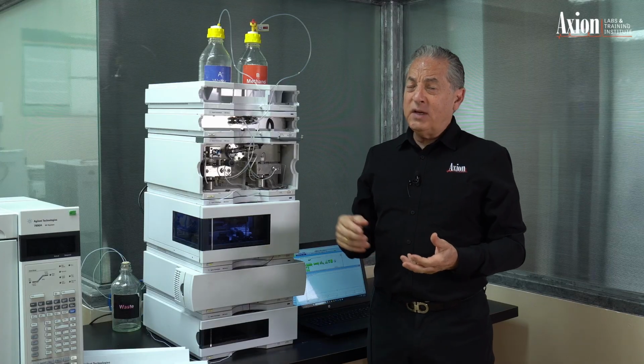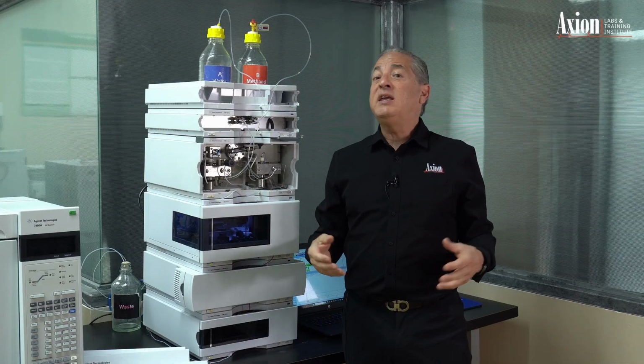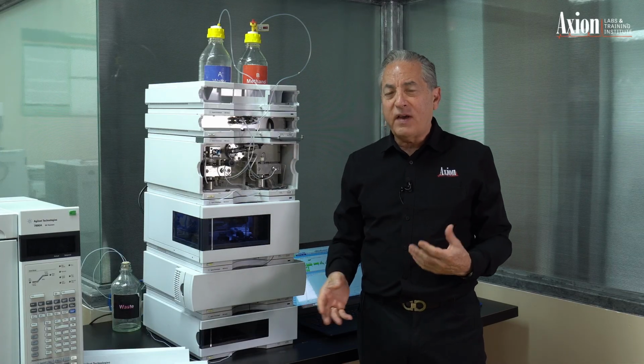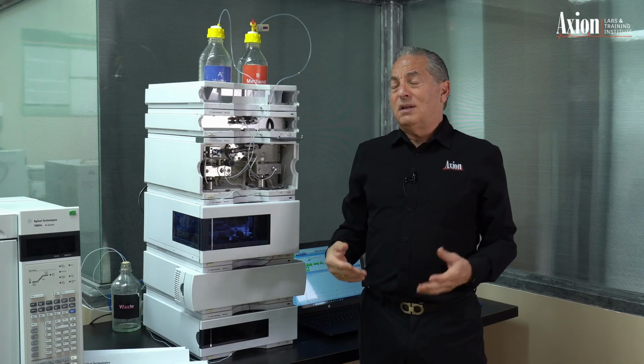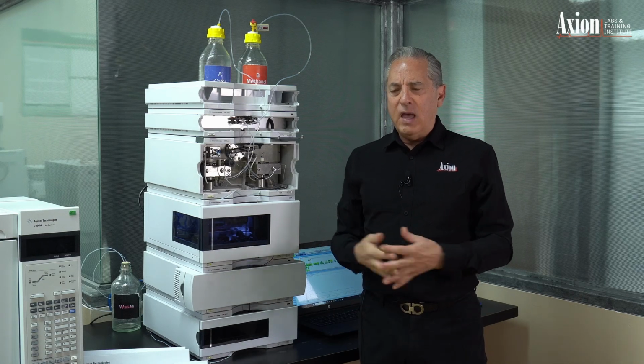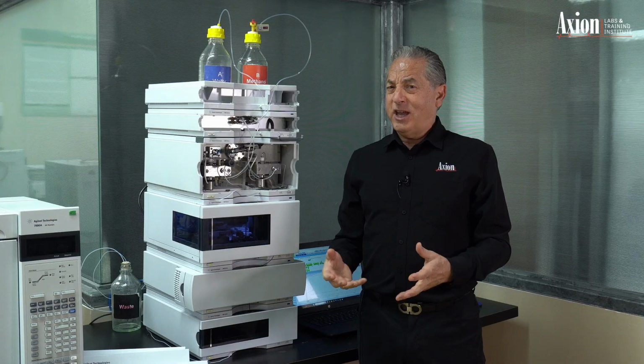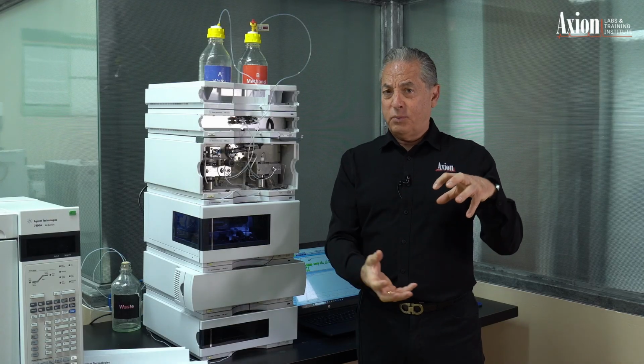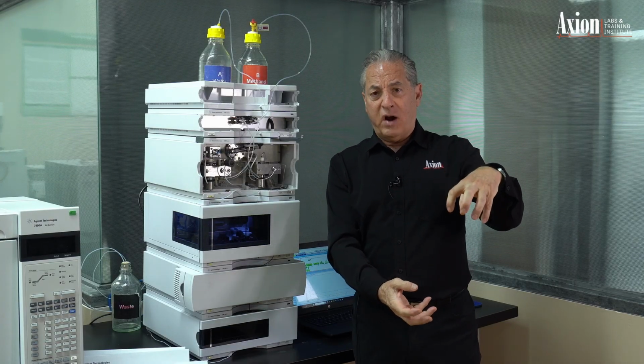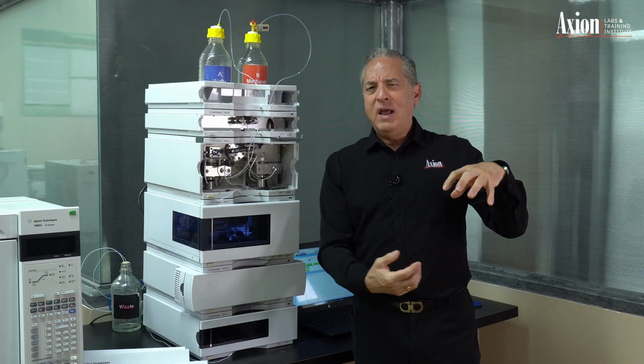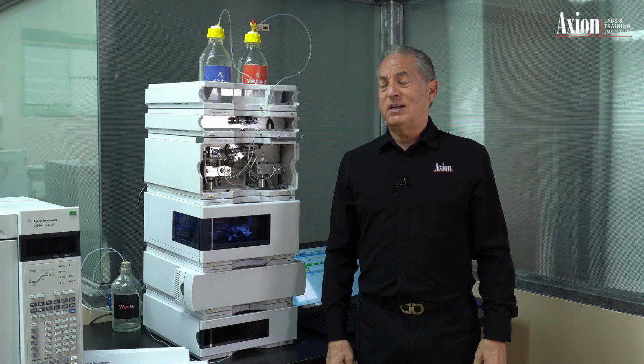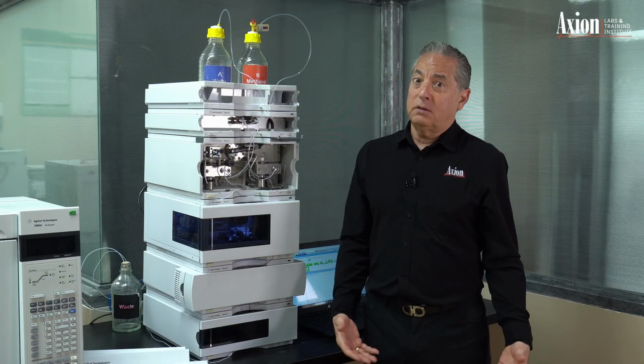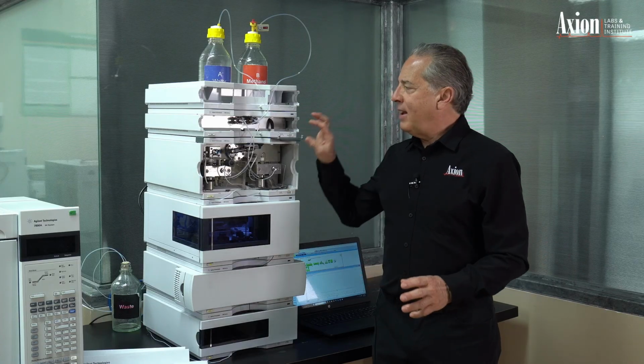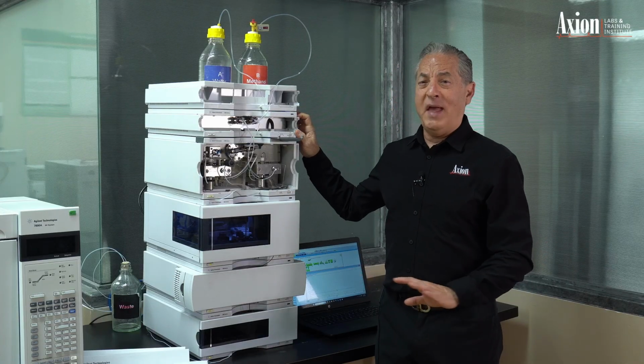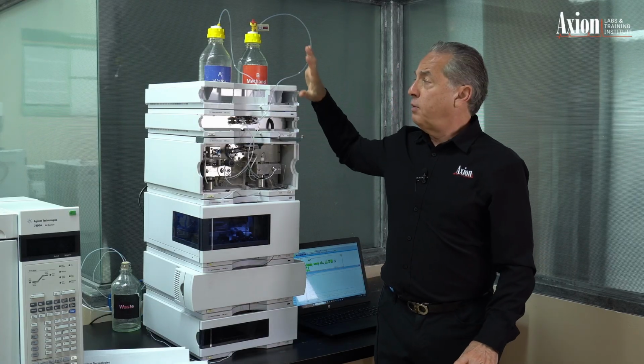In the olden days, we didn't have degassers when I was a kid. We used helium sparging. So you bubble helium through the mobile phase. Works great. It gets to be expensive because you have to use helium. But we also had offline vacuum degassing, where you take your bottle and you put it in a vacuum, like a water aspirator, or maybe use a stirring bar. That is not very efficient. It's a terrible way to go. If you have to do it, if you're old-fashioned, you do it. But with a modern degasser, you don't have to do anything to the mobile phase before you put it in the bottles.